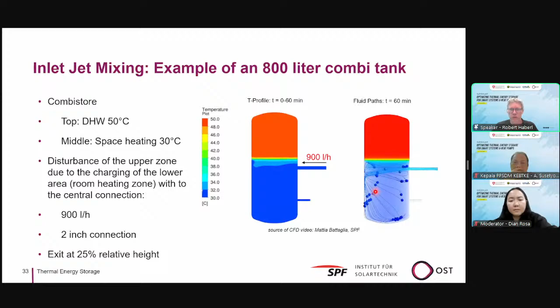If you have only 900 liter per hour, you have significantly less disturbance of the upper zone. The incoming fluid has a much lower velocity and has already been strongly deflected downwards when it hits the opposite storage wall, so that the resulting deflection also takes place mainly downwards, and you keep the upper part hot while charging the lower part to a lower temperature.